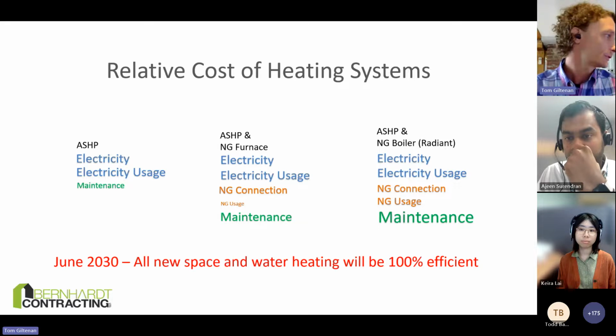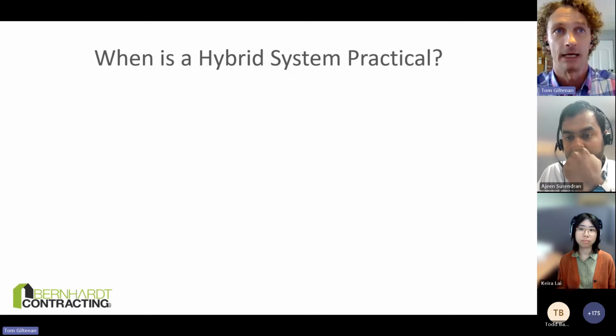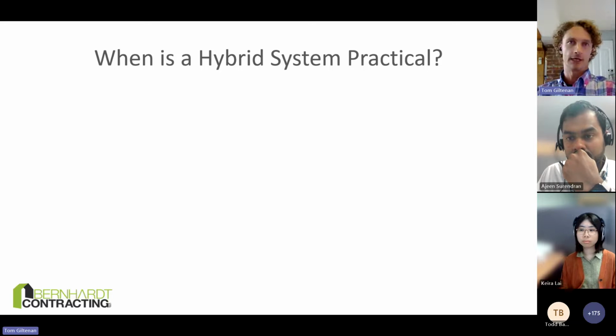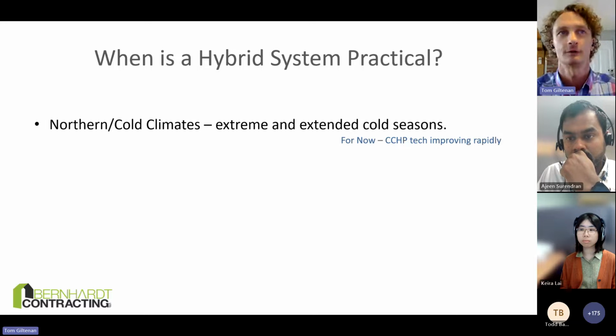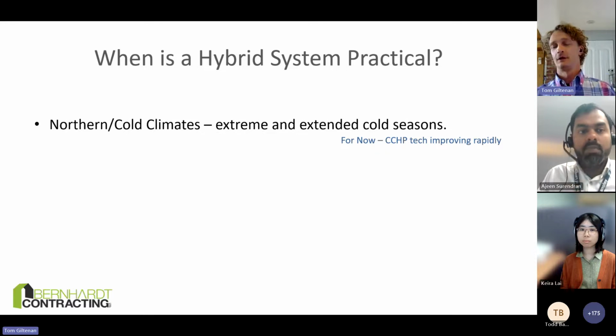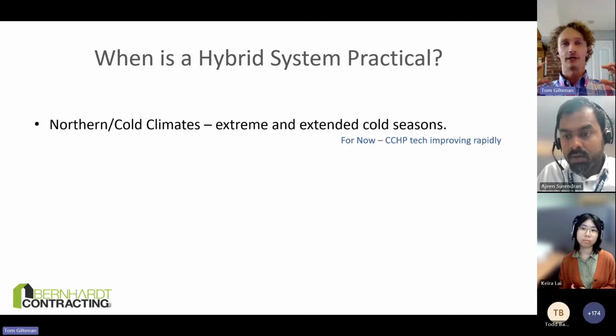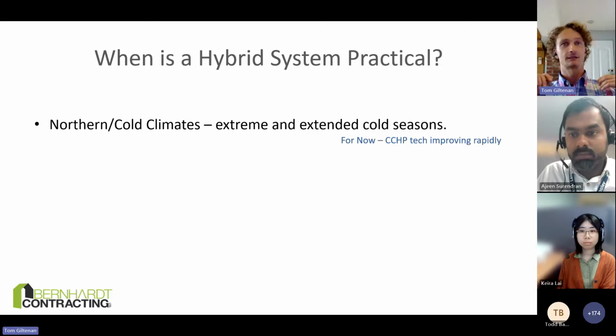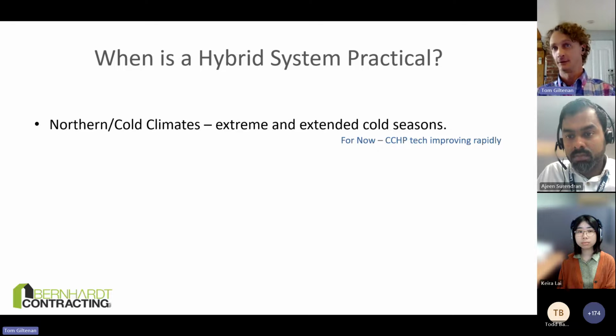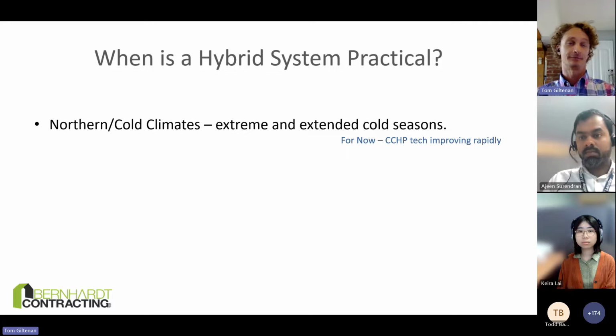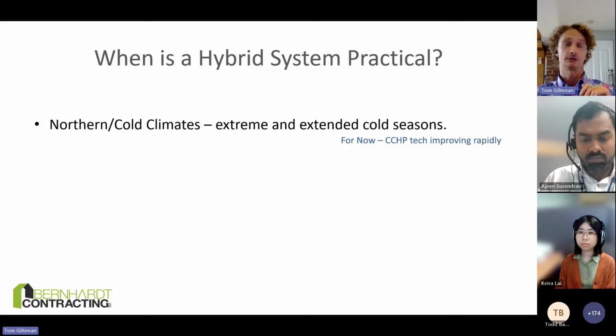So let's move on. So when is a hybrid system practical, you may ask then? Why are they becoming the big rage and all on the front pages of every individual HVAC's websites? And the first and foremost would be in northern cold climates, where you have very cold areas and or cold extended areas. Now this is becoming less and less of a concern as cold climate heat pump technology is coming on fast. In fact, in the last 5 years, some of our cold climate heat pumps from 5 years ago are now in the mainstream as just regular heat pump specifications.